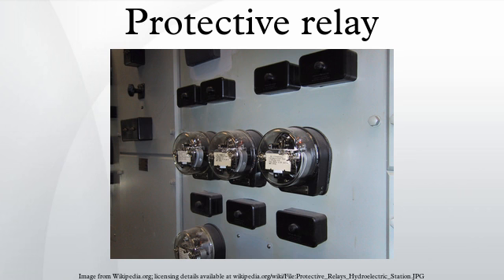Operation principles: electromechanical protective relays operate by either magnetic attraction, or magnetic induction. Unlike switching-type electromechanical relays with fixed and usually ill-defined operating voltage thresholds and operating times, protective relays have well-established, selectable and adjustable time-current operating characteristics. Protection relays may use arrays of induction disks, shaded pole magnets, operating and restraint coils, solenoid-type operators, telephone relay contacts, and phase-shifting networks. Protective relays can also be classified by the type of measurement they make.